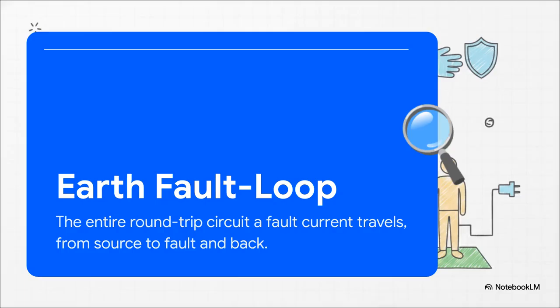Okay, so we've sized our components, right? We've bonded our wet areas. Now for the mathematical proof that our physical safety net will actually work fast enough when disaster strikes. First, we've got to define the loop itself, which is designated as Zs. The Earth fault loop is the entire round-trip circuit that a fault current has to travel. I'm talking all the way from the supply transformer, down the active street wires, through your breaker to the faulty appliance, and then all the way back through the protective earthing conductor and the MEN connection. If there is too much resistance or impedance in this massive loop, the current just won't spike high enough, and your protective breaker simply will not trip fast enough to save a life.